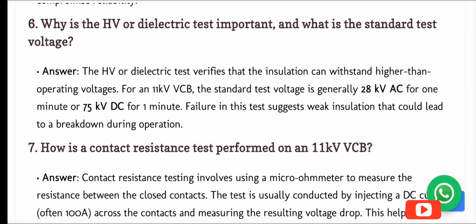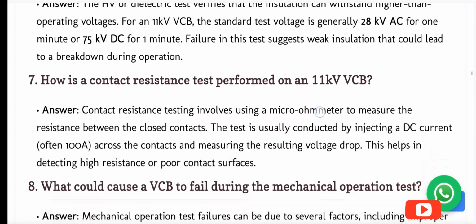6. Why is the HV or dielectric test important, and what is the standard test voltage? Answer. The HV or dielectric test verifies that the insulation can withstand higher than operating voltages. For an 11 kV VCB, the standard test voltage is generally 28 kV AC for 1 minute or 75 kV DC for 1 minute. Failure in this test suggests weak insulation that could lead to a breakdown during operation.